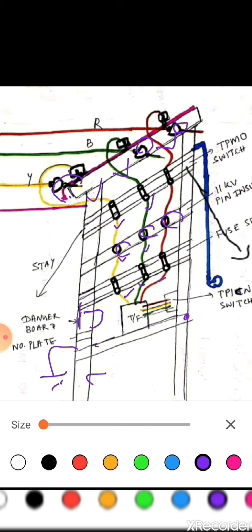Next, concreting of poles. So we need to concrete the pole for the mechanical strength. Next one is TPMO switch. So this is our TPMO switch, that is triple pole mechanically operated switch. Next, painting has to be done for the poles. So 2 liters of paint is required. Next is fuse set. These are the fuse set. So one set of fuse set is required.